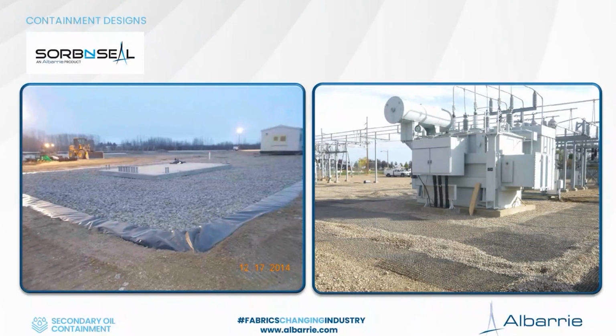The capacity for the mat itself is always the same. As I mentioned earlier, the mats themselves have negligible capacity when it comes to the overall containment design. They're there to create a barrier and manage chronic leaks. The actual capacity of the containment is determined based on what you want to contain, how much oil is in the equipment itself, and that determines the footprint - how big, wide, and deep the containment has to be to contain that total amount of fluid.